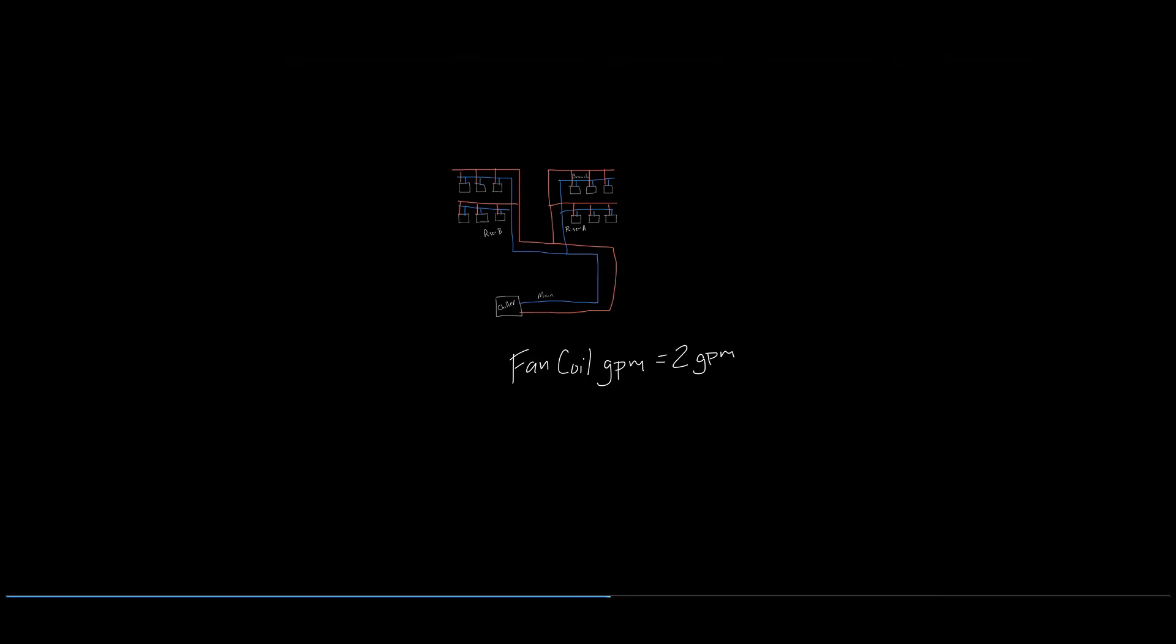So where exactly should the balancing valves be located in the system? Let's start with the risers. In order to control the rate of flow back to the boiler or chiller, each riser return line will receive a balancing valve to control the flow.